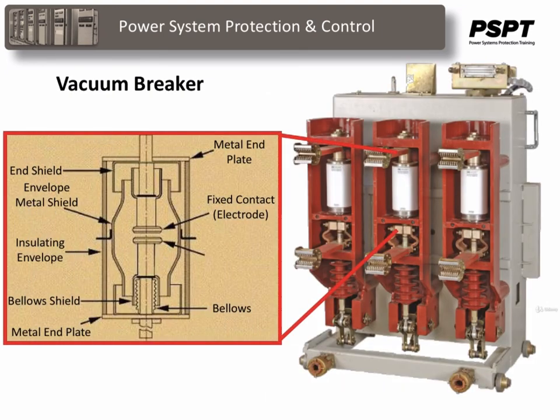The service life of a vacuum circuit breaker is much longer than any other type of circuit breaker. There's no chance of a fire hazard as there is in oil circuit breakers, and it is a much more environmentally friendly breaker than one that contains SF6 gas. Replacement of the vacuum interrupter part of the circuit breaker is almost as convenient as changing a fuse in a fuse panel.